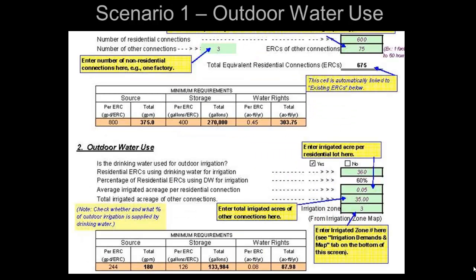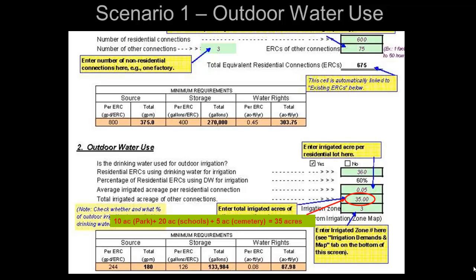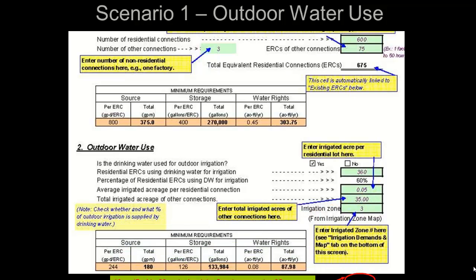Next, we'll perform the calculations for outdoor water use. This community is in Zone 3, so we enter 3 in this field. 360 of the 600 residential connections are used for irrigation, so we enter 360 in this field. The percentage of residential ERCs using drinking water for irrigation is automatically calculated at 60%. Next, we need to enter the average acreage per residential connection — we'll enter 0.05 for the data given. We then need to total the acreage for the other connections. In our scenario, the area of the park, school, and cemetery equals 35 acres. By entering this data, the minimum outdoor capacity requirements are automatically calculated.